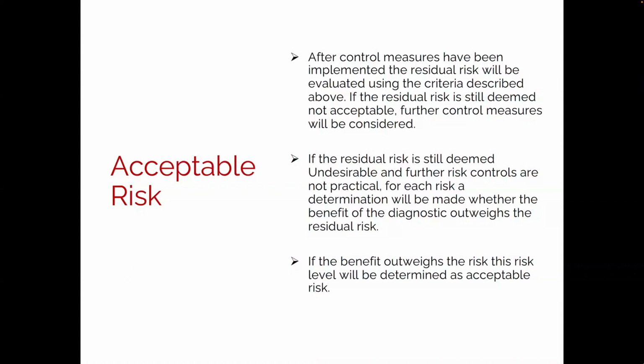And obviously, if you're in that red zone where it's unacceptable, you really have to justify getting out of that red zone, even if you have to do a redesign of the product to reduce either the severity, if that's possible, or drive the probability of harm to a lower level.